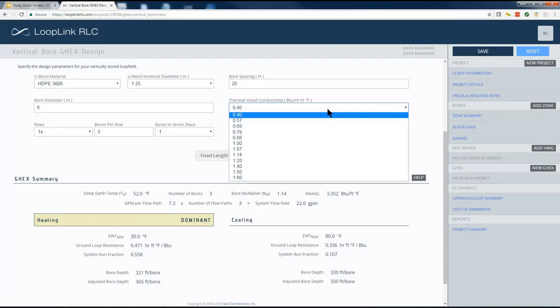It's simply bentonite with a certain amount of water pumped into the hole in slurry form, and it sets up like peanut butter. But as you can see, standard bentonite grout doesn't have the greatest conductivity. For any value above a 0.4, that's considered to be a thermally enhanced grouting product. So to get your bentonite grout to have a conductivity that's higher than 0.4, you have to add something to the mix. So you either add silica sand or you add graphite. Those are really the two options that you'll see in the industry.